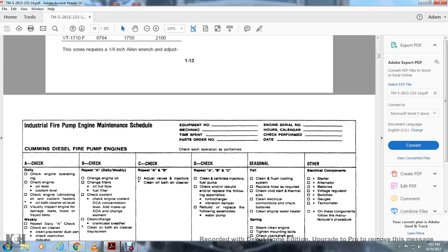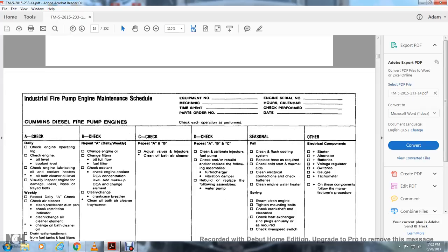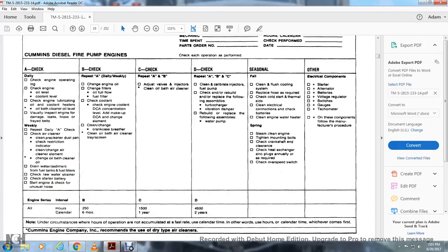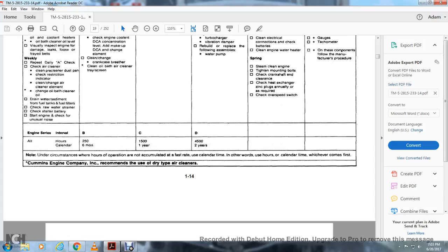Clean the electrical connections. Check the batteries. Clean the engine water heater. Spring: steam clean the engine. Tighten mounting bolts. Check the crankshaft end clearance. Check the heat exchanger zinc plugs annually as required, and check the overspeed switch. Engine, other electrical components: starter, alternator, batteries, voltage regulator, switch gauges, and tachometer. On these components, follow the manufacturers' procedures. All right, engine service intervals are in hours and calendar: 250 hours or 6 months, 1500 hours or 1 year, 4500 hours or 2 years.